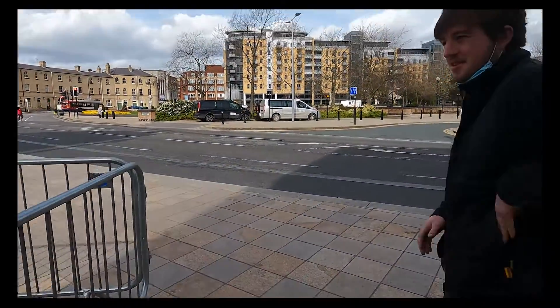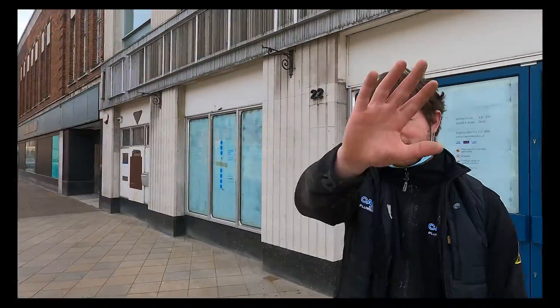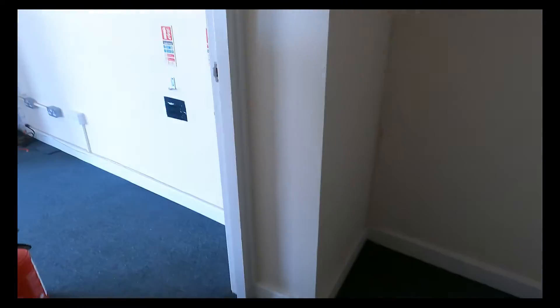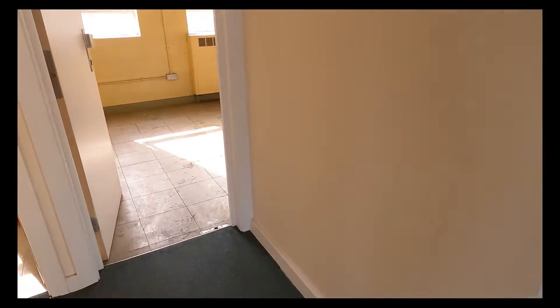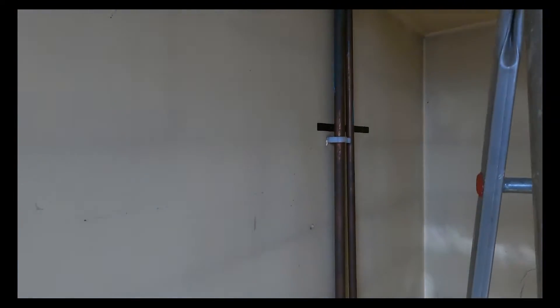We've just popped outside for a bit of fresh air because it's probably blowing that plant around. You can see it's in the hole now. It's your number one apprentice again Matty. So we're just back in the building - Matty just shouted down to me there's a bit of water coming through where the tanks are. So we should go upstairs and investigate - they are the old galvanised tanks in here as well. He's getting a bucket and dried that up, he's already been up. That looks like it's been an old expansion cap top. That's my cold main run - I've traced that back from downstairs. I've got my heating supplies there.